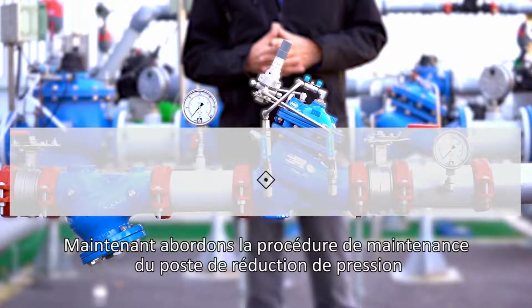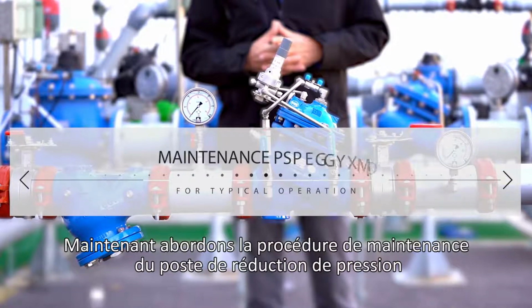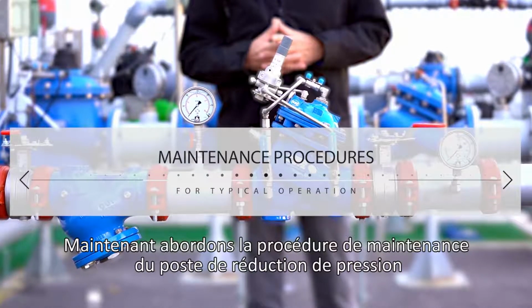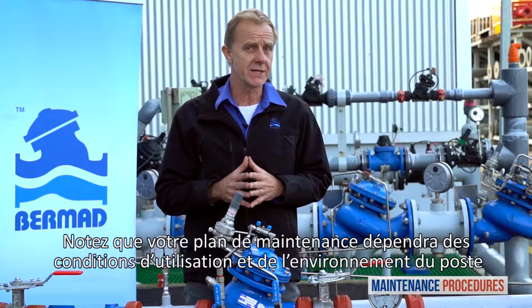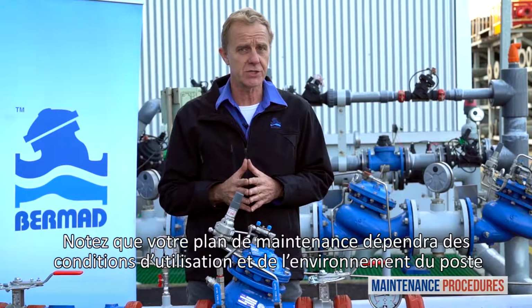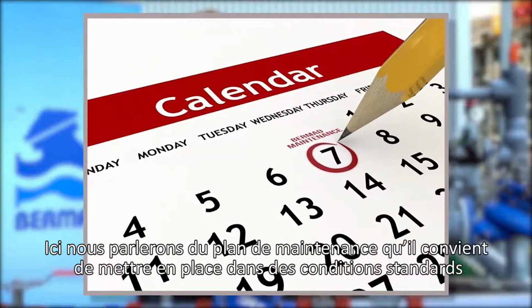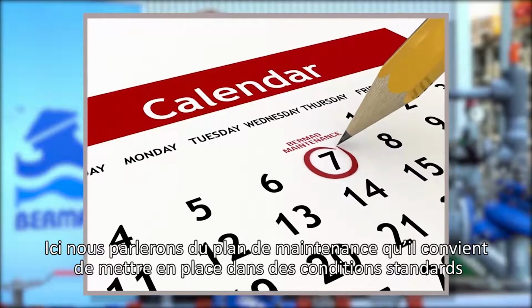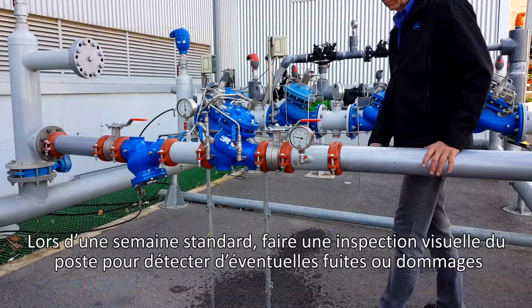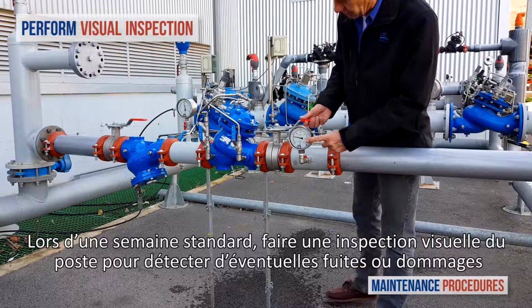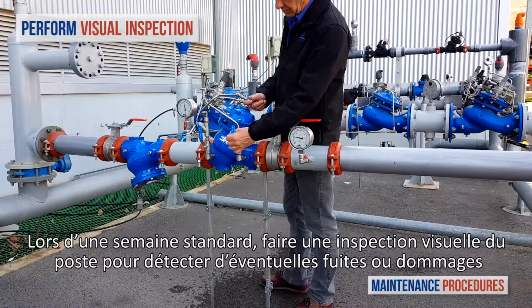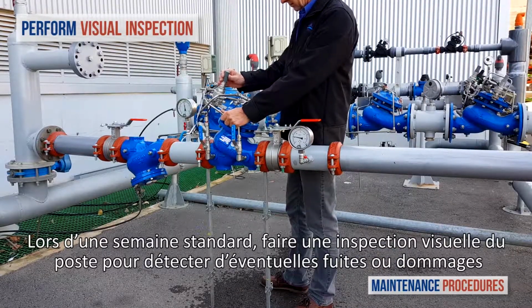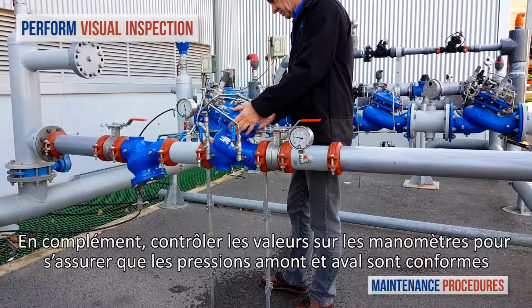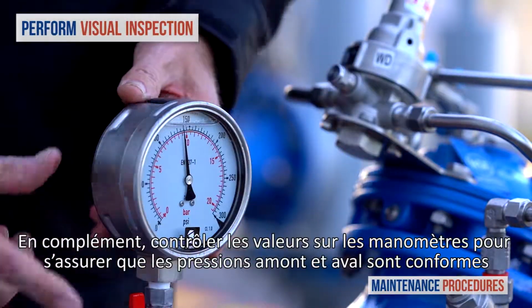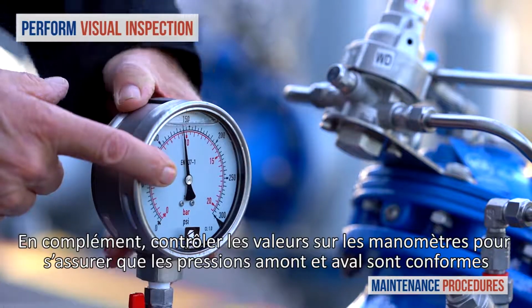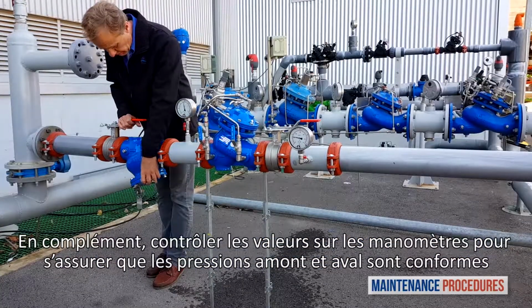Now let's discuss maintenance procedures for the BERMAD PRV pressure reducing station. Note that your schedule for preventative maintenance depends on the actual conditions of use and the station's environment. Here we discuss a schedule suited to a valve operating under average conditions. On a weekly basis, perform a visual inspection of the station and check for leaks or external damage. In addition, observe the unit's pressure gauges to make sure that the pressures upstream and downstream are as they should be.